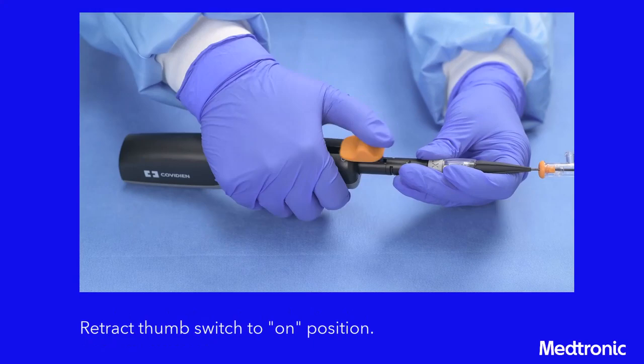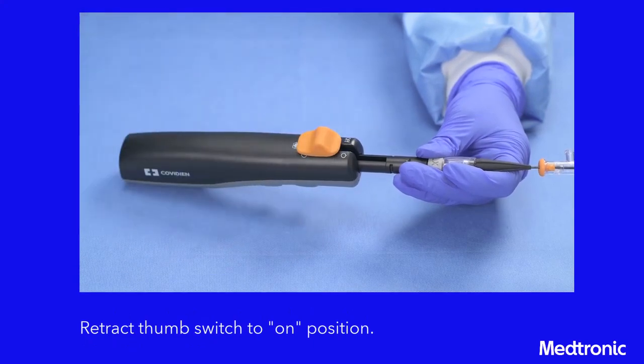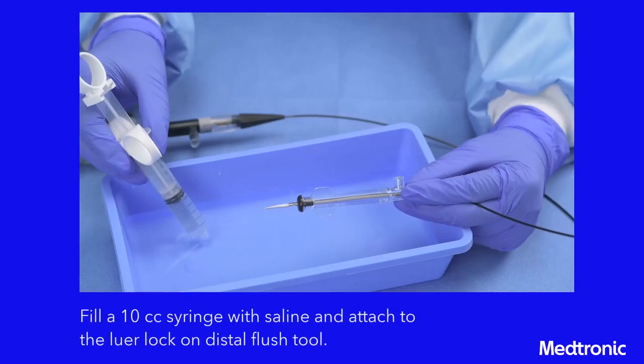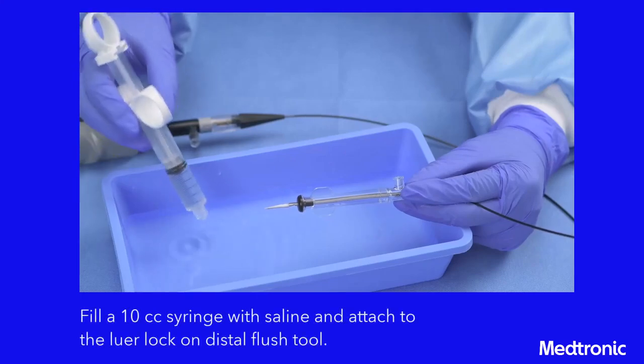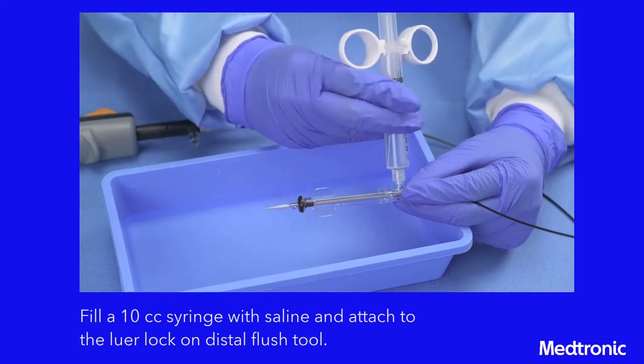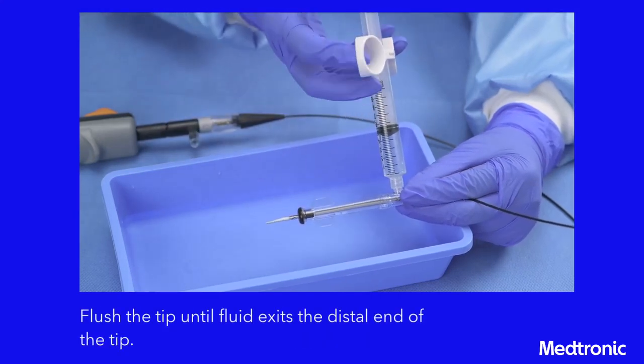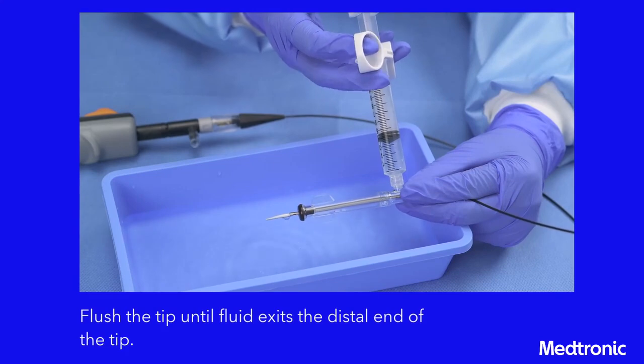Retract the thumb switch to the on position to expose the cutter within the cutter window. Fill a 10 cc syringe with saline and attach it to the luer lock on the distal flush tool. Flush the tip until fluid exits the distal end of the tip.